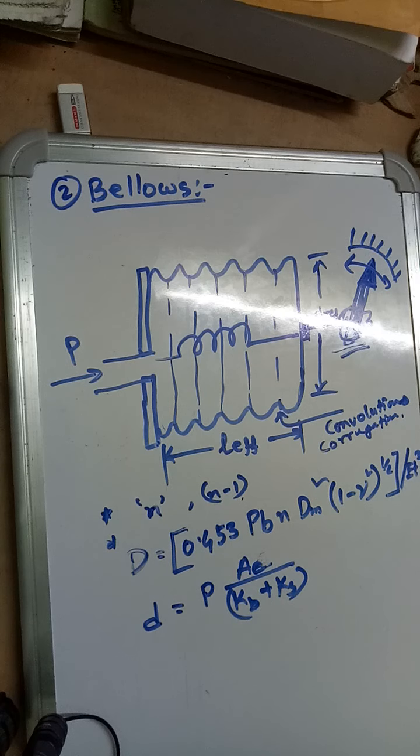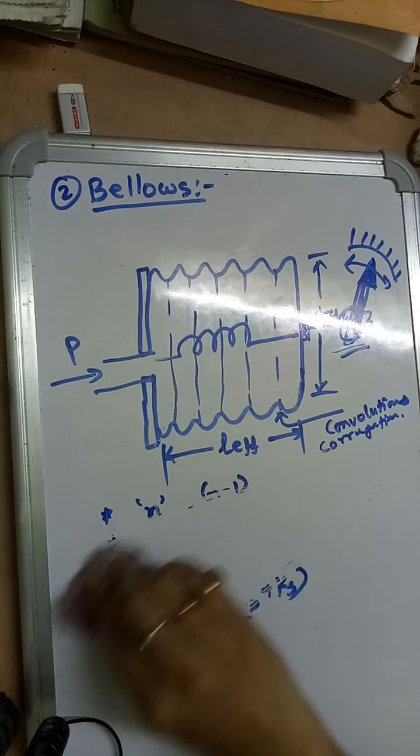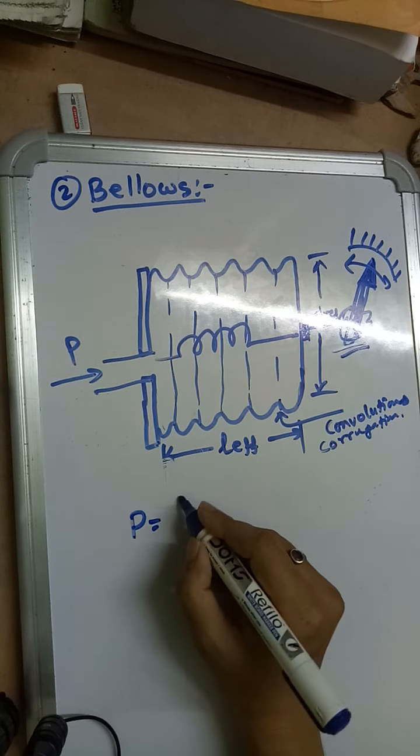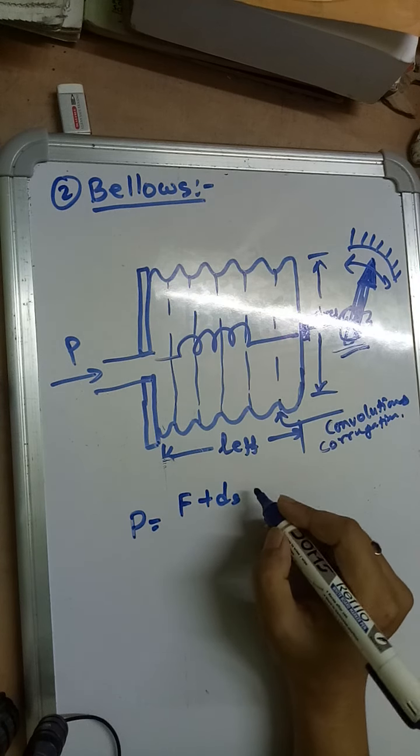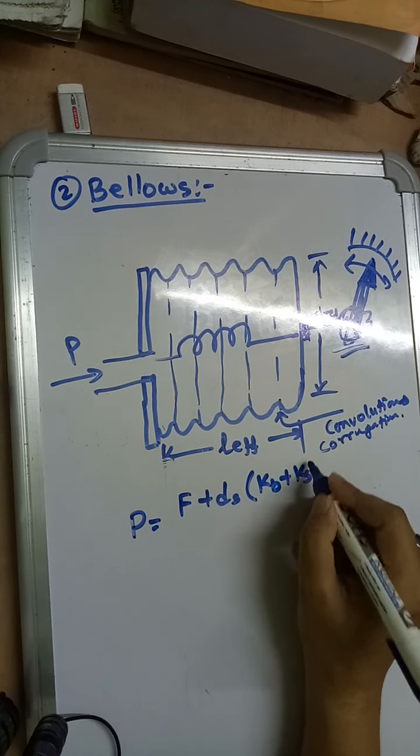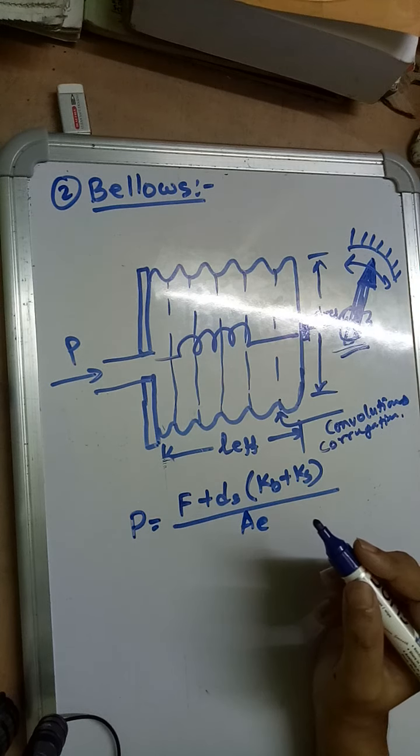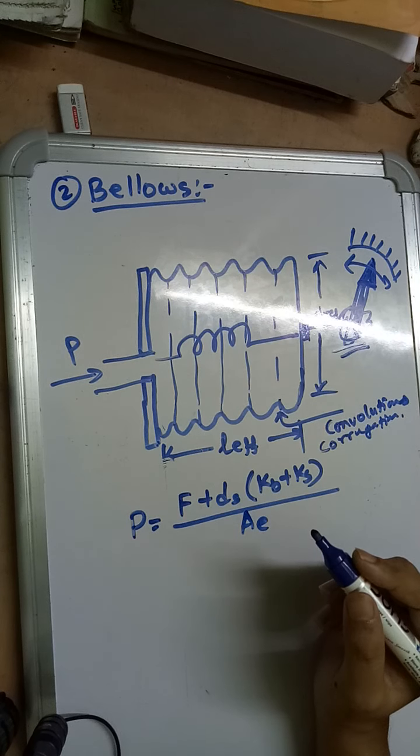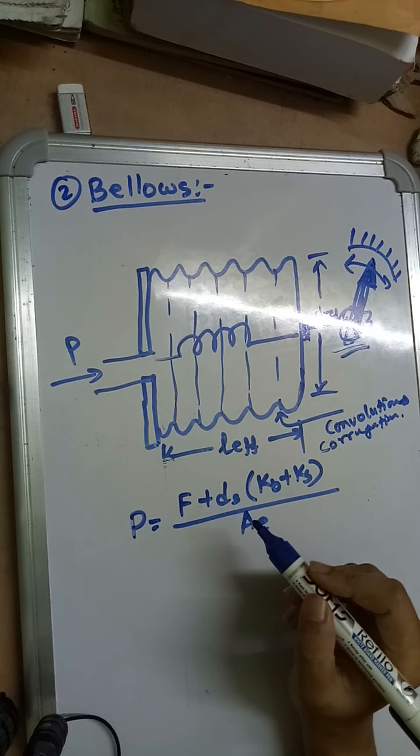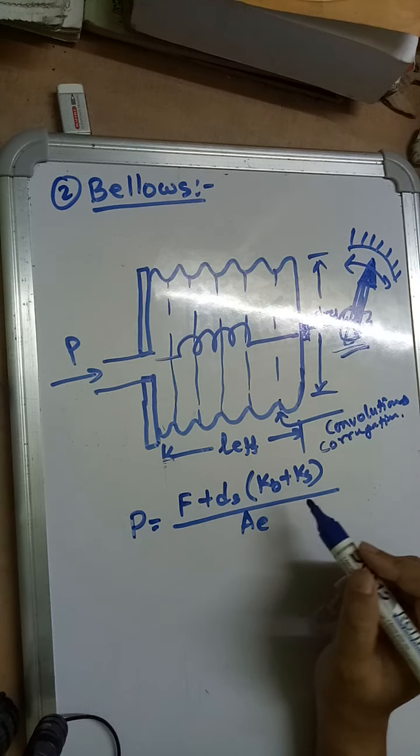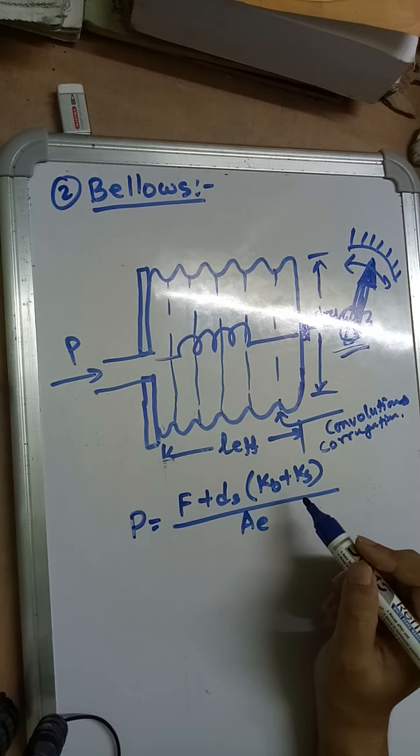If the bellows assembly is to be operated by some electrical switch or mechanism at its free end, then the pressure will be given by p = (F + d_s × (k_b + k_s)) / A_e. Here, F equals the force required to operate the switch or mechanism, d_s equals deflection required to operate the switch mechanism.